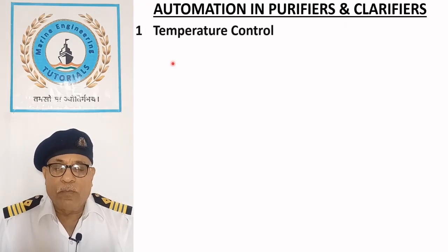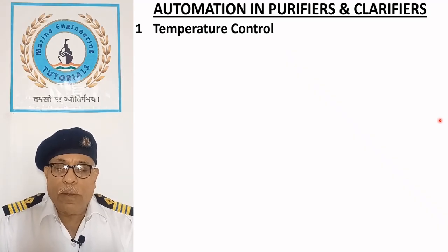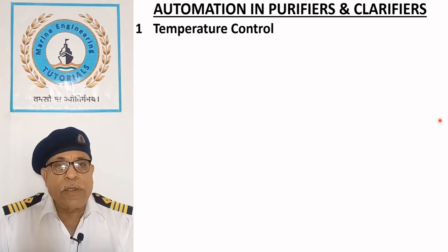Temperature control. As per the set point, PID temperature controller automatically regulates the flow of steam passing through the oil heater to maintain the desired temperature at the heater outlet.